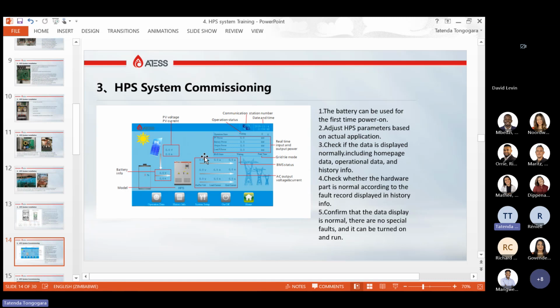On the screen of our HPS system, this is the screen. Your PV voltage, PV current, you see the values here. When you're designing your system, your VMP should be at least 100 volts higher than your battery maximum voltage. Please take note of that. For efficient optimum charging of your battery with PV, your VMP should be at least 100 volts higher than your battery max voltage. Any value between 100 to 200, but at the same time you are not supposed to exceed 800 volts on your VMP.